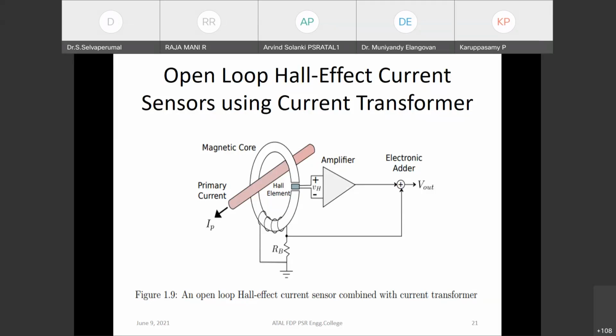A novel configuration was proposed, right? Where the output voltage of the Hall element and the current transformer winding are amplified and added using an electronic adder to get the final output voltage. So this voltage signal is proportional to the primary current, right? This configuration was further modified to get a bandwidth of 30 megahertz, right?